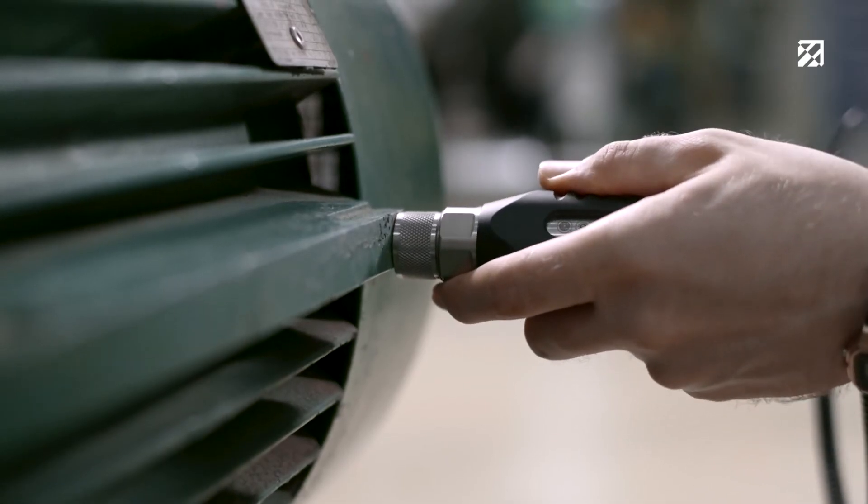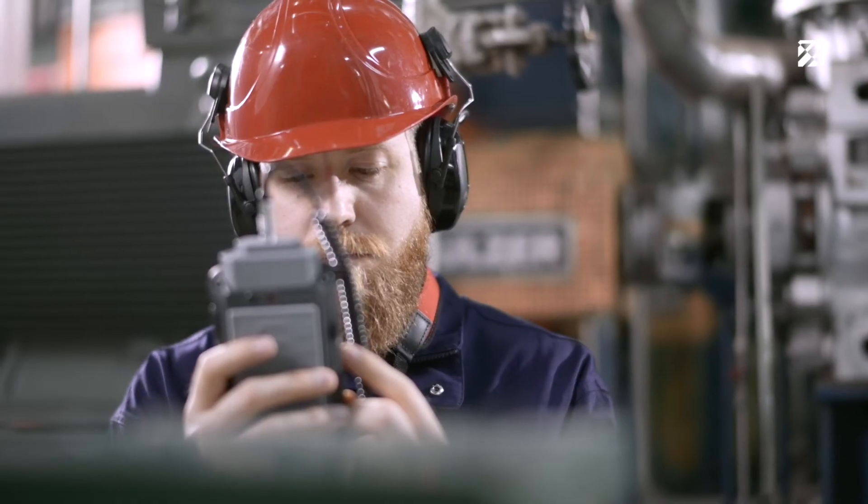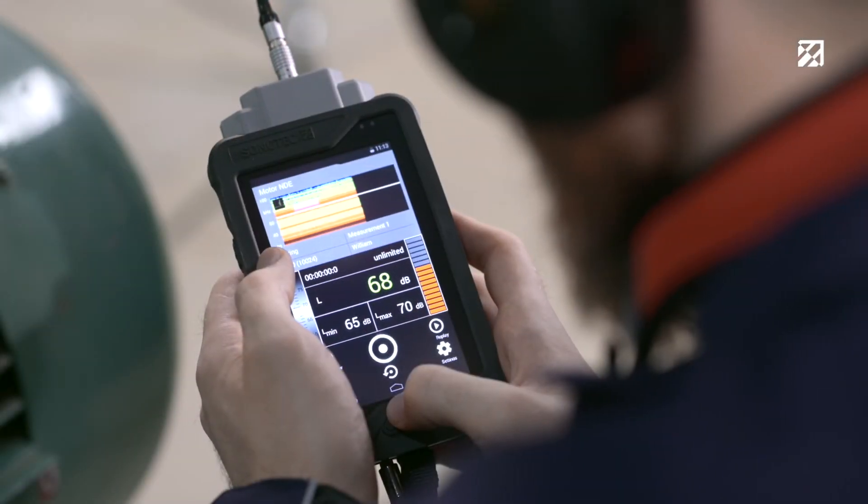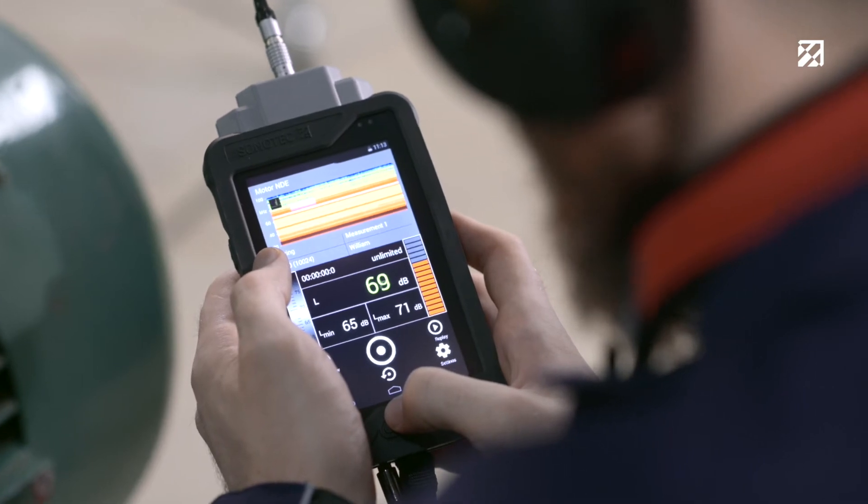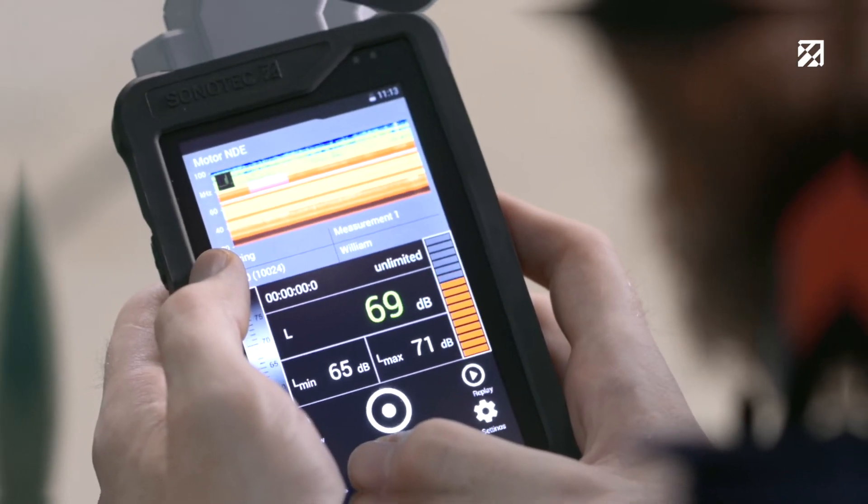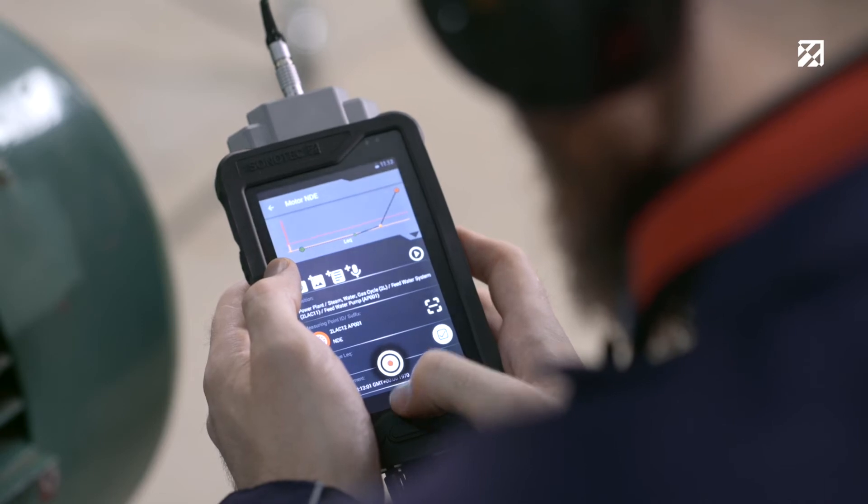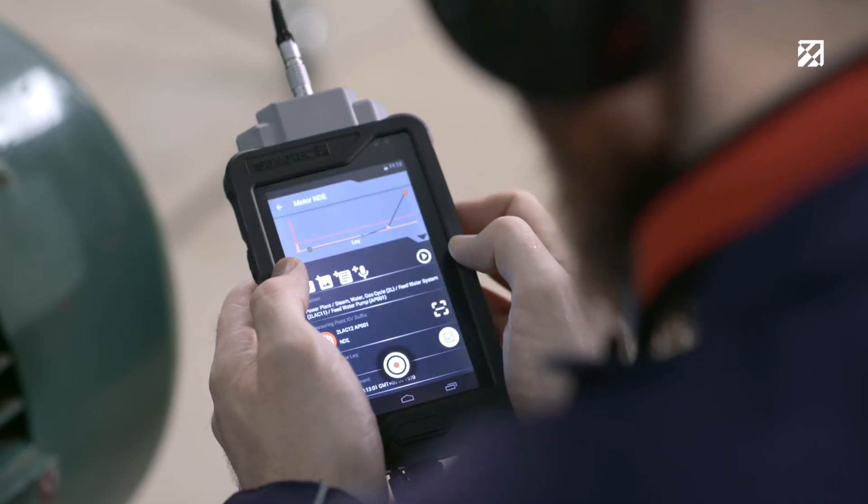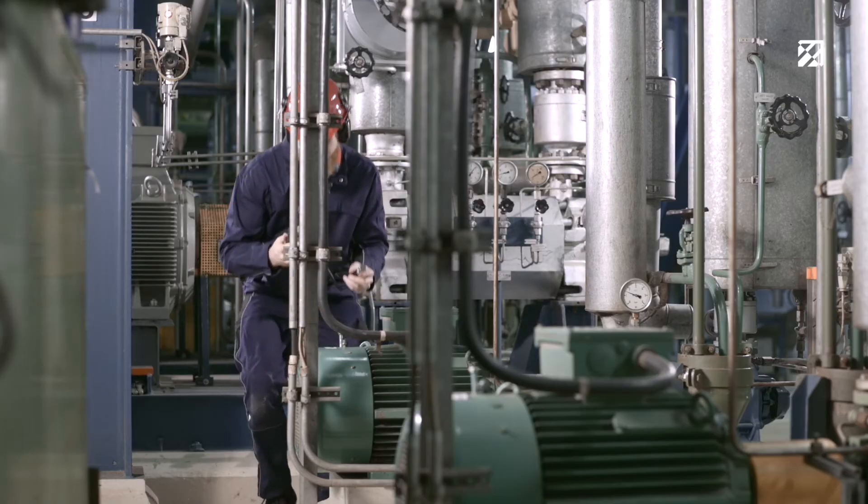The BS40 ultrasonic sensor is coupled with a flat magnet to record the ultrasonic signal. Start the measurement. When comparing with previous tests, the maintenance technician immediately notices on-site that the level values have changed significantly. Make a note of it and add a photo.